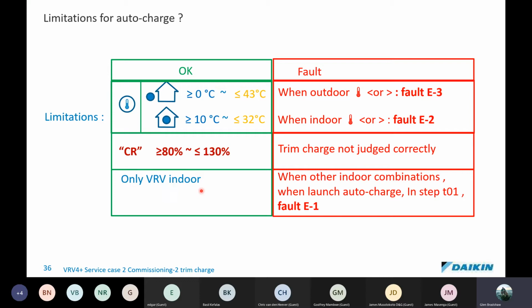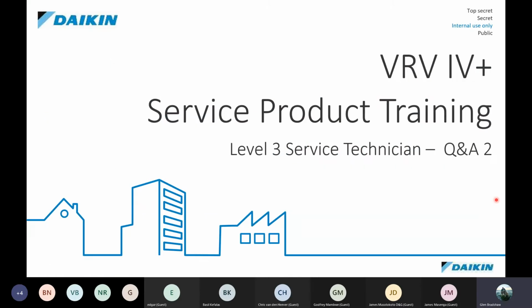In other words, if we have a combination on the system of hybrid air handling units, Hydroboxes, or RA units, then you cannot do an auto charge for those systems. Then it is critical that you do the manual charge, which is done by adding the gas manually into the system. So keep your mind on those things.